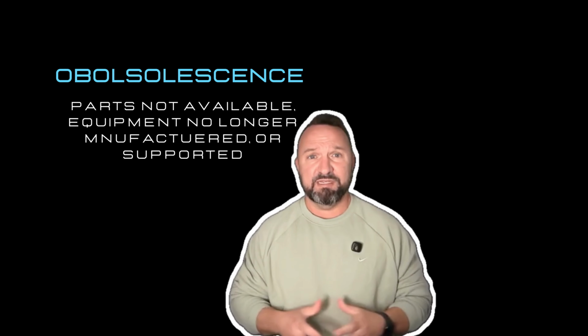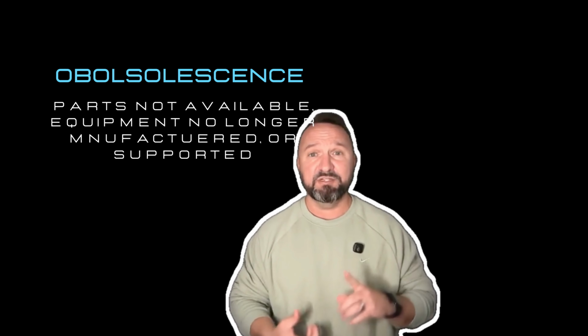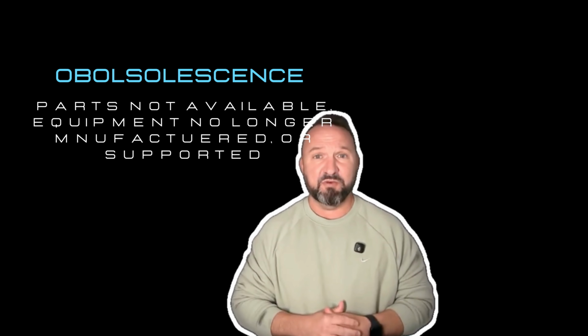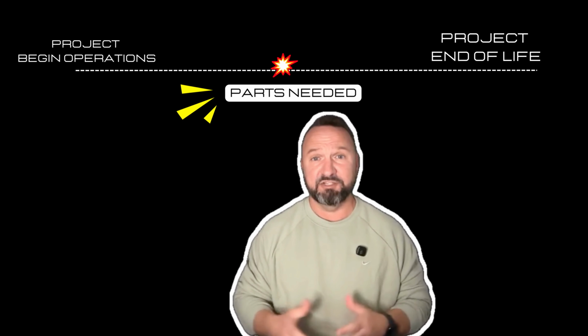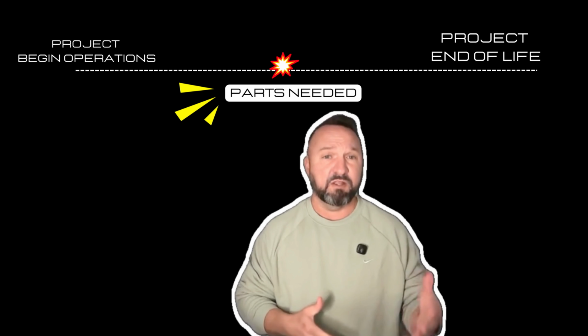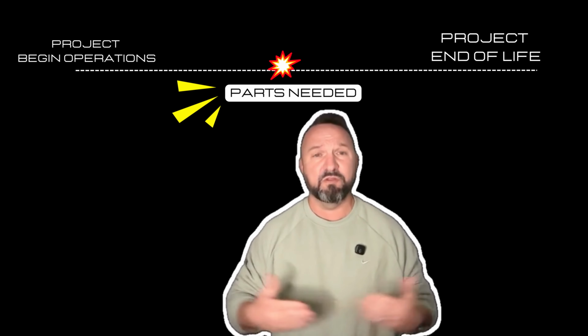For utility scale plants, this is serious because they're designed to operate 25, 30, maybe 30 plus years. And that creates a serious challenge because inverters are often a 7, 10, 15-year design life. Batteries may need augmentation within 8 to 12 years, and electronics like controllers and boards, well, these fail over time. Without planning for obsolescence, operators can find themselves unable to repair critical equipment, leading to long outages and lost revenue.